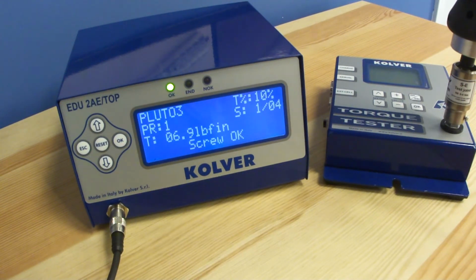It's also important to remember that even after the calibration procedure has been done, if any of the individual program parameters such as speed, torque percentage or hard or soft joint are manipulated, the calibration procedure needs to be done again to give an accurate representation of the real-world calibration being seen on the torque tester. This completes the calibration procedure for Kolver's EDU2AE TOP series.